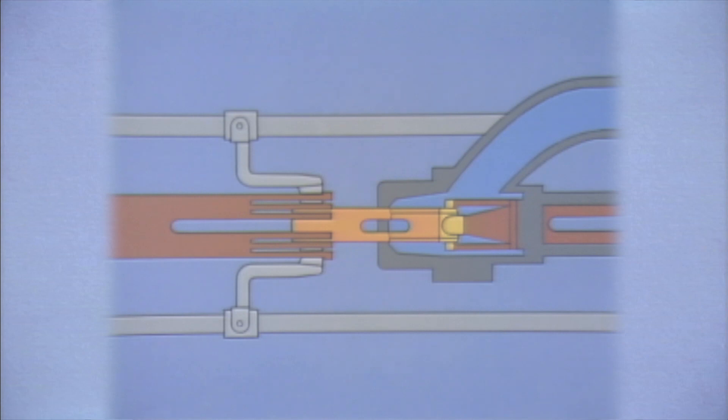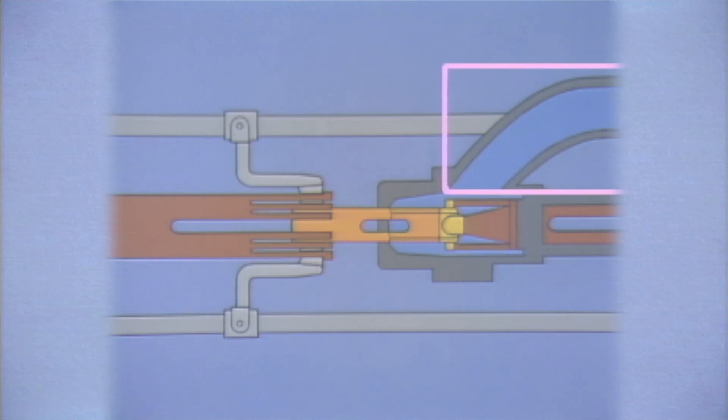We can get a more detailed picture of how the arcs are extinguished if we look more closely at one of the sets of contacts. The main features in this simplified illustration include a hollow moving contact, stationary contact fingers gripping either end of the moving contact, an arcing horn, and a blast tube.